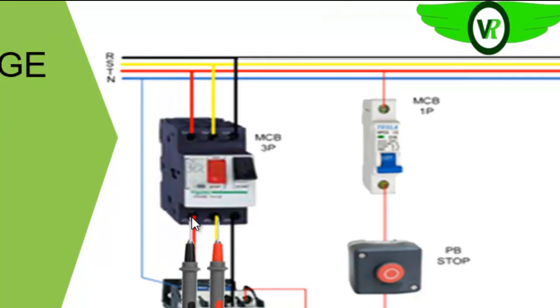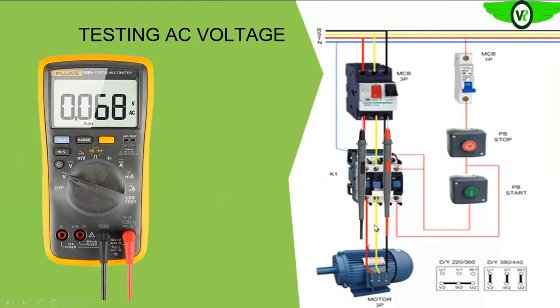So line 1 and line 2, which is phase to phase, is supposed to give you 415 volts. Okay, so now remember that what you are doing now is testing the output of that circuit breaker. So when the circuit breaker is closed, you expect to have that 415 volts at that output. So also it is when you test between line 1 and line 3, line 2 and line 3. Okay, so you are supposed to have that 415 volts. So if you are not having that 415 volts, while your input is correct, your contactor, okay, your circuit breaker is faulty. The circuit breaker that is feeding the electric motor, as you can see. Okay, so it's faulty.